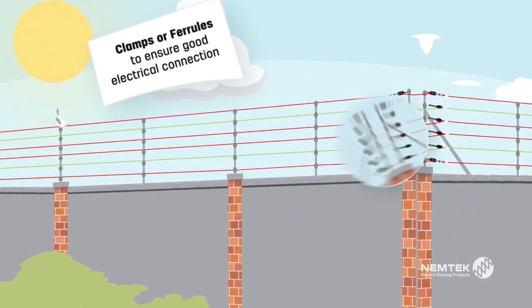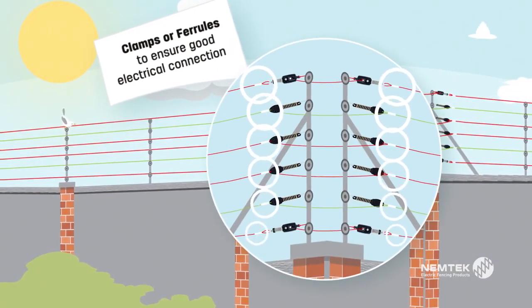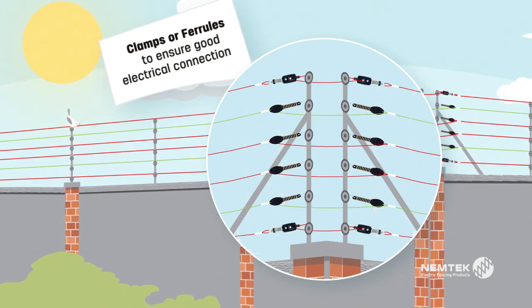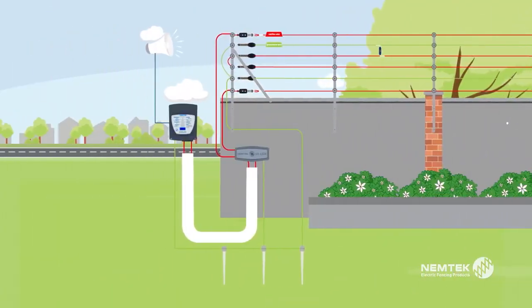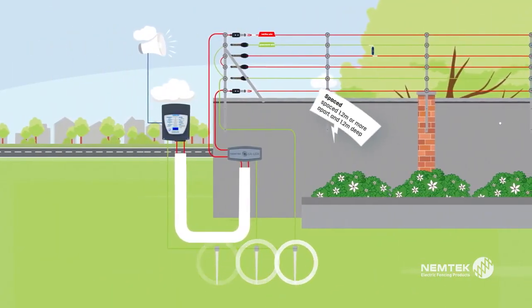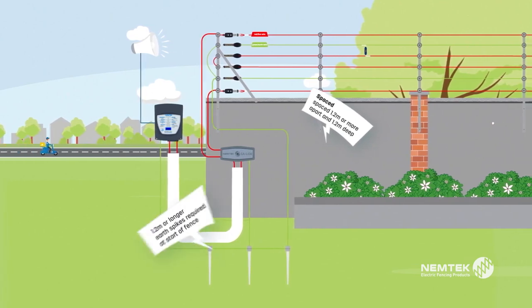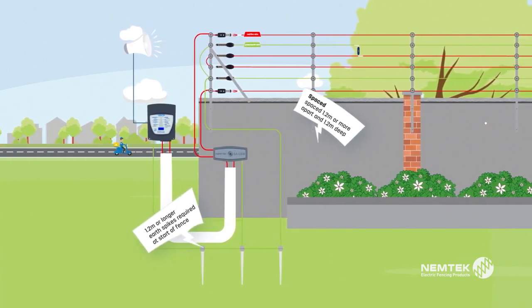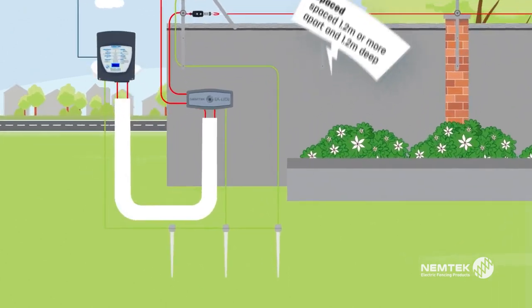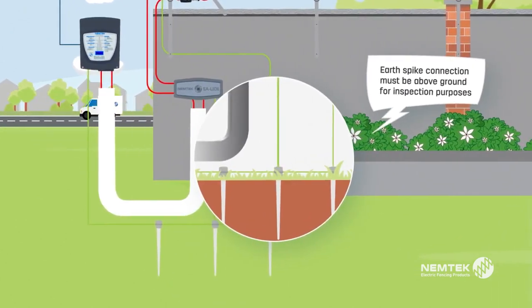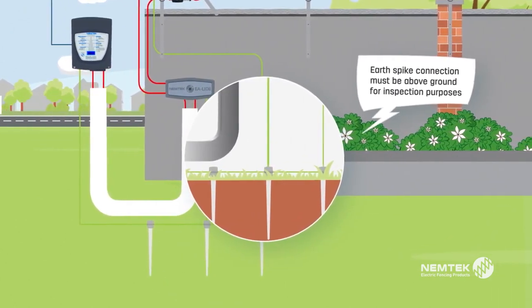Clamp or ferrule all wire joints for good electrical connection and seal them where there is a chance of corrosion. Install at least 3 earth spikes at the beginning of the fence to ensure good earthing and a shock when live wires are touched. Add additional earth spikes in areas with poor earthing conditions.